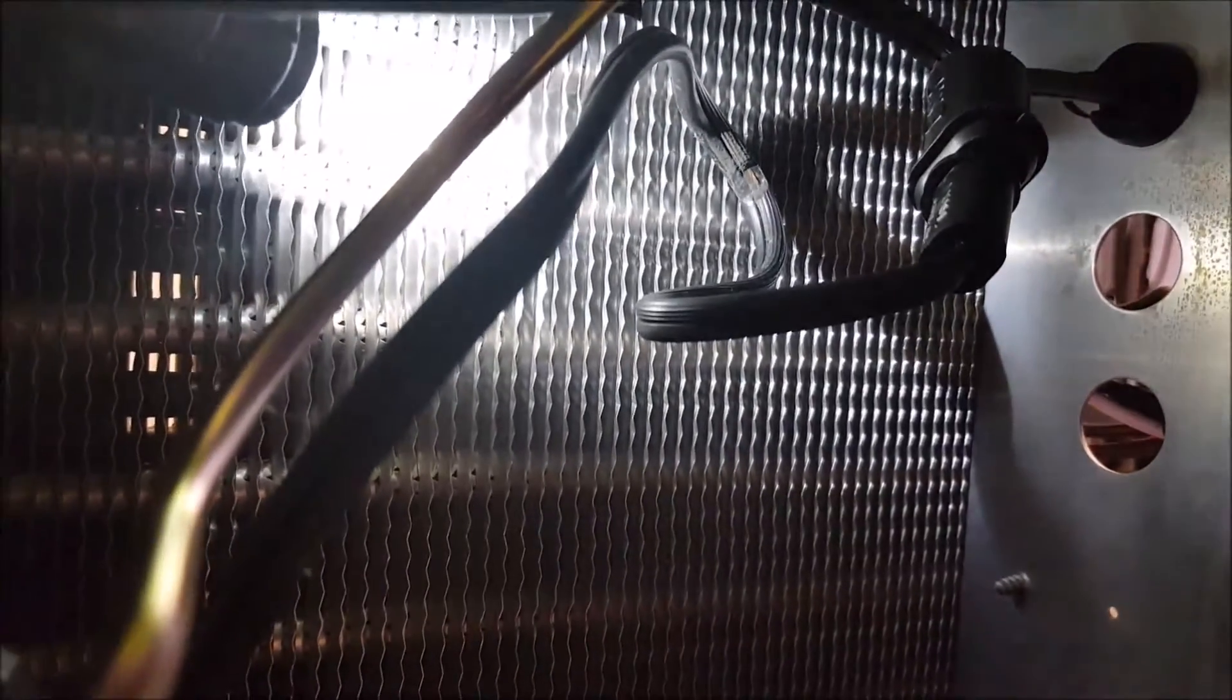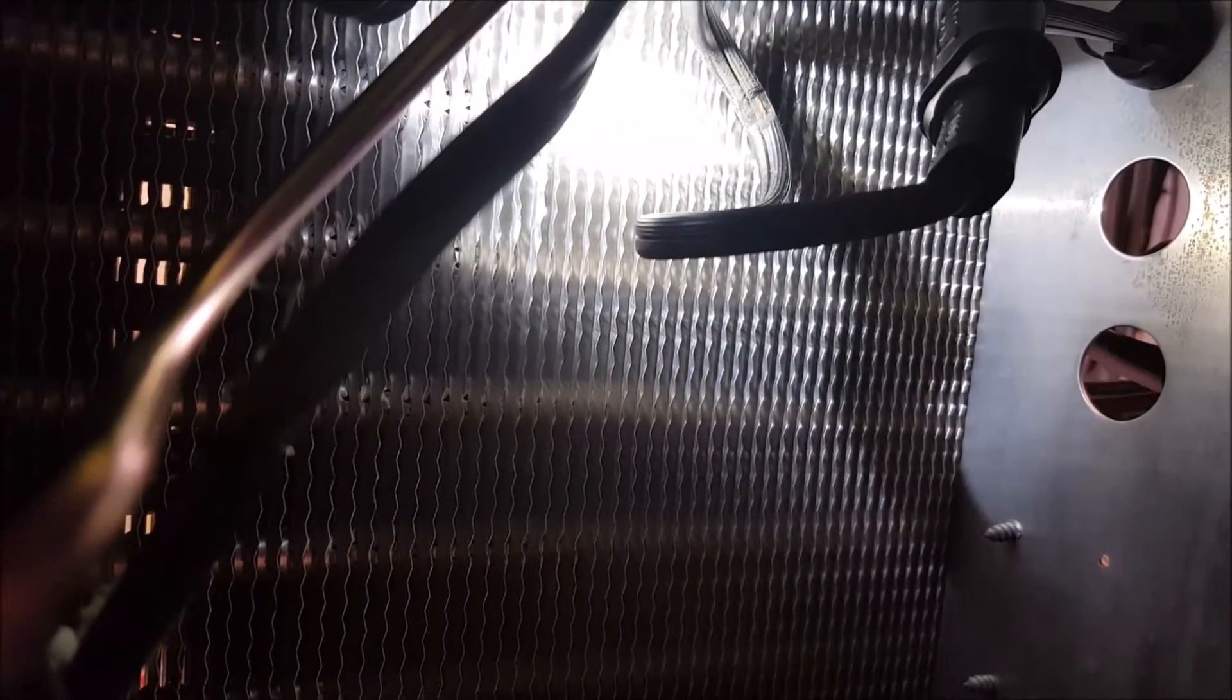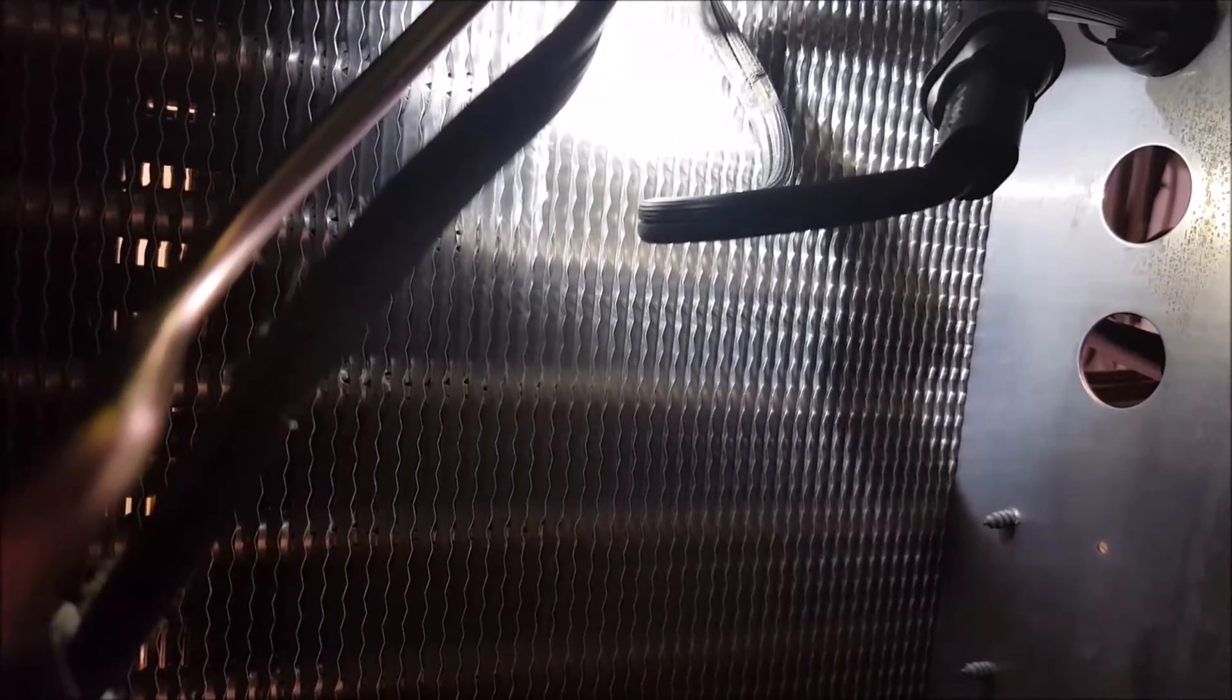That wire has got to be fixed. I can see the copper in that wire. So any water touches it along with the metal, you're going to conduct electricity. It's going to short out the unit, trip the breaker or something. So that's got to be repaired.